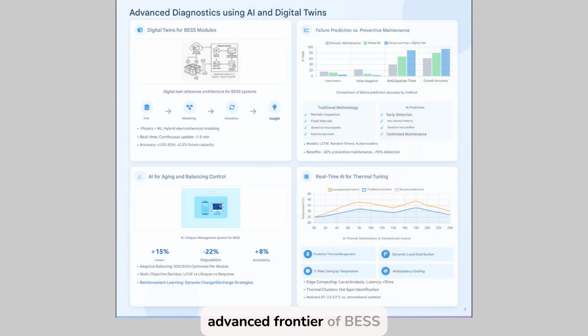We are now at the most advanced frontier of BESS systems operation engineering, the integration of artificial intelligence and digital twins to maximize availability, efficiency, and service life while minimizing failures and OPEX. A digital twin is a dynamic virtual representation of the physical system, powered by real-time data and predictive models. The features of the digital twin shown are hybrid physical plus machine learning modeling, continuous update between 1 and 1.5 minutes, operating accuracy of plus or minus 1.5% for state of charge, SOH, and plus or minus 2.3% for future capacity. It allows for anticipating degradation, simulating thermal responses, and automatically adjusting set points before failure occurs.